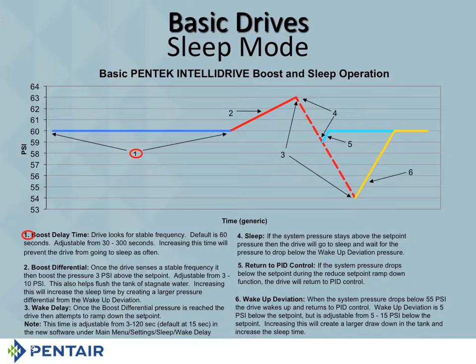How do we do that? We boost the pressure. We boosted 3 psi. You can adjust it, but we boosted 3 psi. Now, you'll notice number 3. Number 3 is a little confusing because it says wake delay. And basically what it really means is this. If the drive drops that 3 psi right away, it just continues to run in PID mode, okay? If it goes up that 3 psi and stays there, now you're going to go to sleep. In other words, what it's going to do, it's going to say, I'm at 63 psi, I'm going to wait 15 seconds. You decide, do I go to sleep or do I continue running? And that's what that number 3 is.